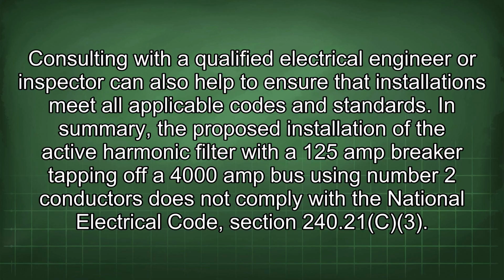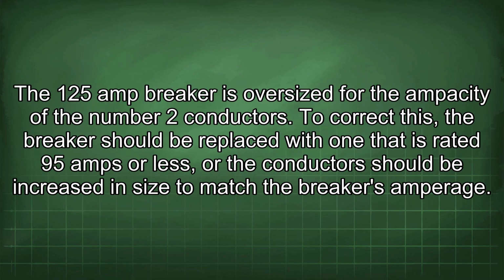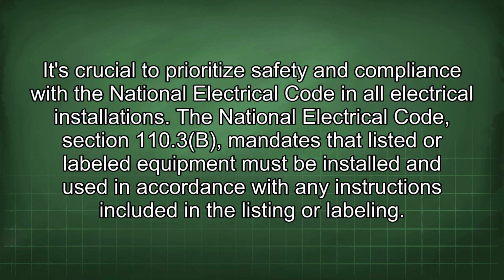codes and standards. In summary, the proposed installation of the active harmonic filter with a 125 amp breaker tapping off a 4000 amp bus using number 2 conductors does not comply with the National Electrical Code, section 240.21(C)(3). The 125 amp breaker is oversized for the ampacity of the number 2 conductors. To correct this, the breaker should be replaced with one that is rated 95 amps or less, or the conductors should be increased in size to match the breaker's amperage. It's crucial to prioritize safety and compliance with the National Electrical Code in all electrical installations.